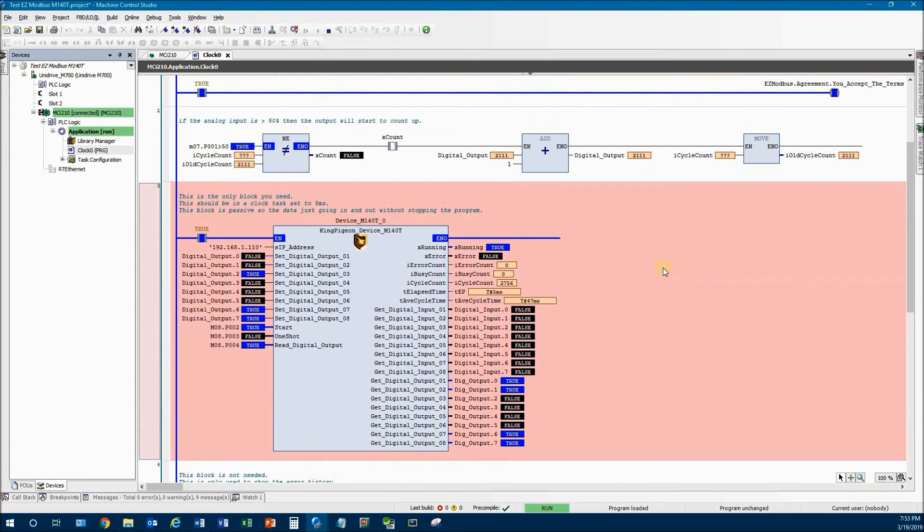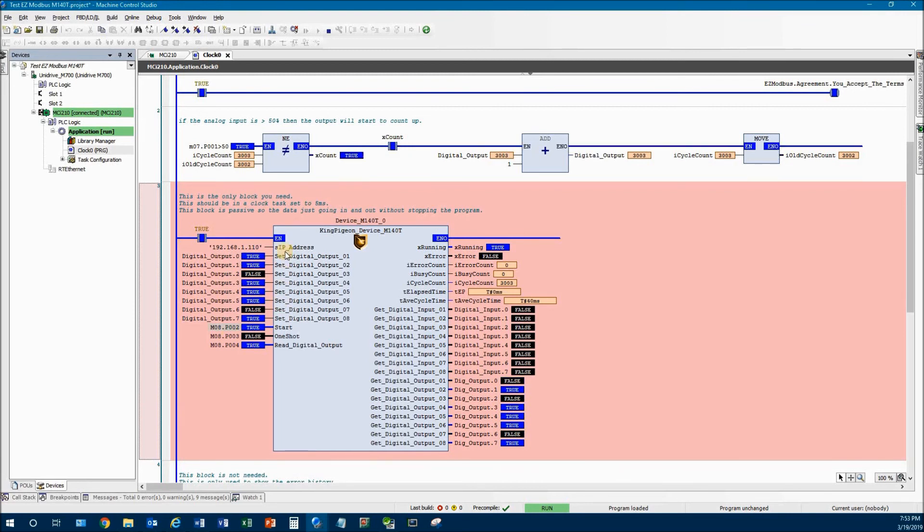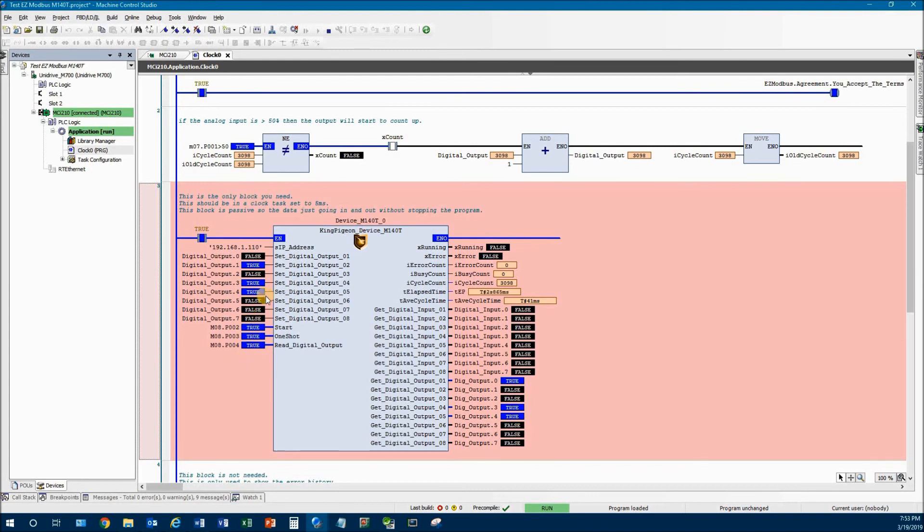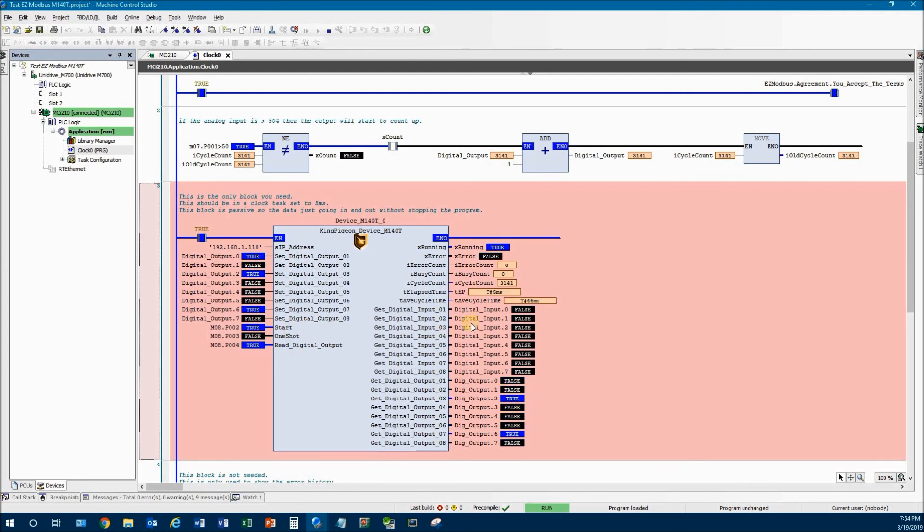And the last thing to talk about is this thing called one shot. Most of the time you use it just for debugging, or maybe you have a case where you only want it to read or write to a particular block once. And then maybe you change the IP address or something. So if this is on, you need to hit the start. And it's rising edge every time you want it to send and read a message. So what it does is it does this one, then it does this one, then it does this one, then it finishes. Okay. So I'm going to turn one shot off. Let it run normally.